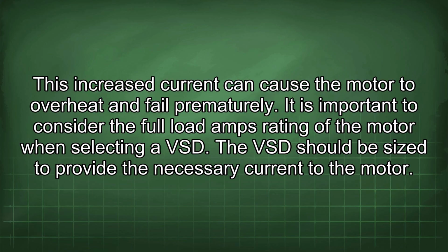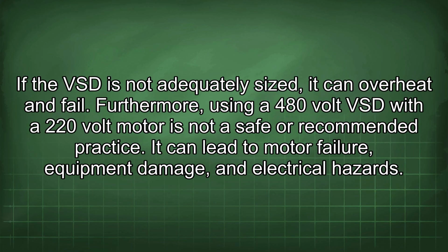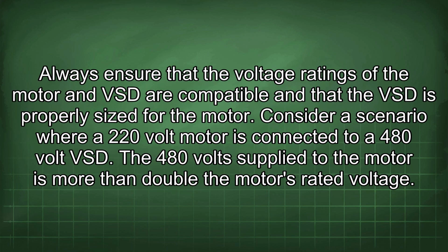It is important to consider the full load amps rating of the motor when selecting a VSD. The VSD should be sized to provide the necessary current to the motor. If the VSD is not adequately sized, it can overheat and fail. Furthermore, using a 480-volt VSD with a 220-volt motor is not a safe or recommended practice. It can lead to motor failure, equipment damage, and electrical hazards.